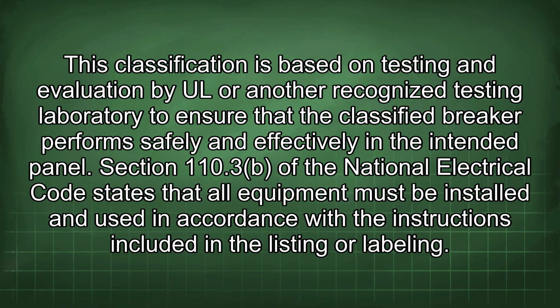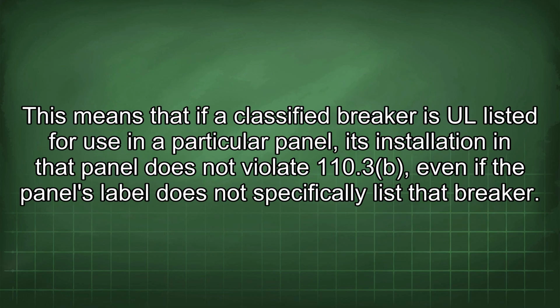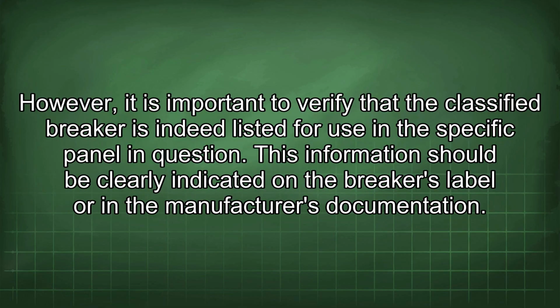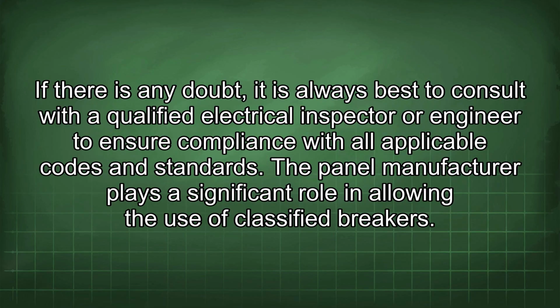Section 110.3 of the National Electrical Code states that all equipment must be installed and used in accordance with the instructions included in the listing or labeling. This means that if a classified breaker is UL listed for use in a particular panel, its installation in that panel does not violate 110.3, even if the panel's label does not specifically list that breaker. However, it is important to verify that the classified breaker is indeed listed for use in the specific panel in question. This information should be clearly indicated on the breaker's label or in the manufacturer's documentation. If there is any doubt, it is always best to consult with a qualified electrical inspector or engineer to ensure compliance with all applicable codes and standards.